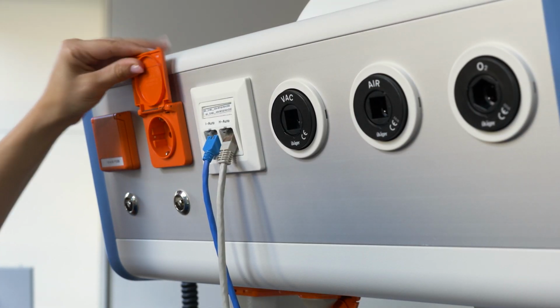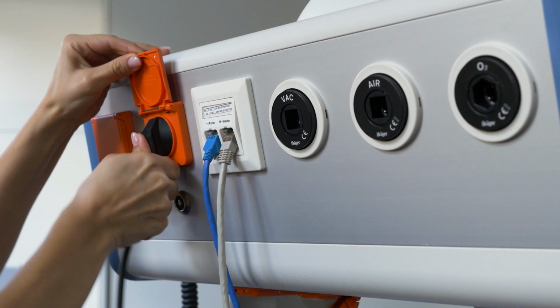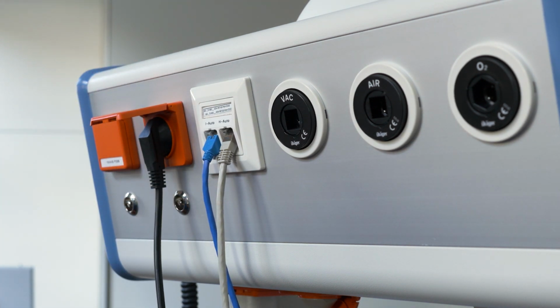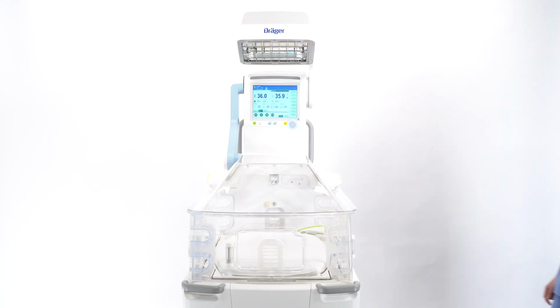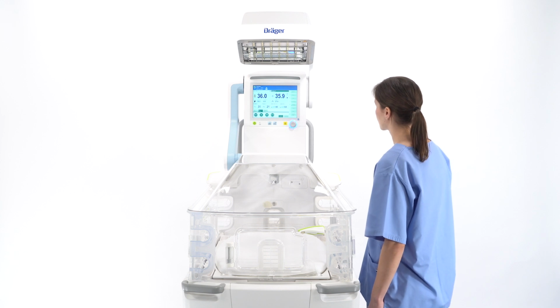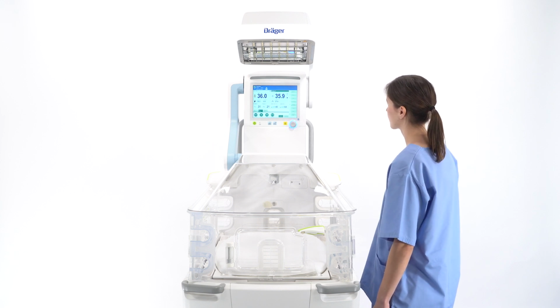Transport should be performed with a minimum of 2 people and the patient's condition constantly monitored. When transport is over, connect the mains power cable to an outlet at the new location. The battery charges automatically. Check the patient's status, device settings, and therapy values, and adapt if necessary.